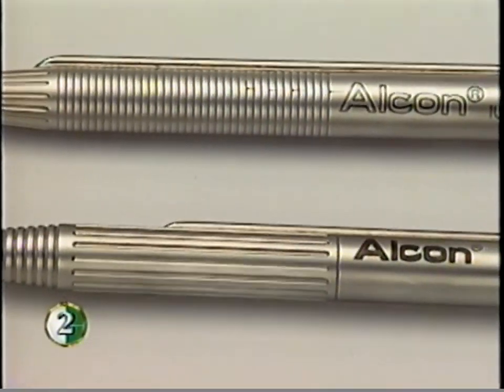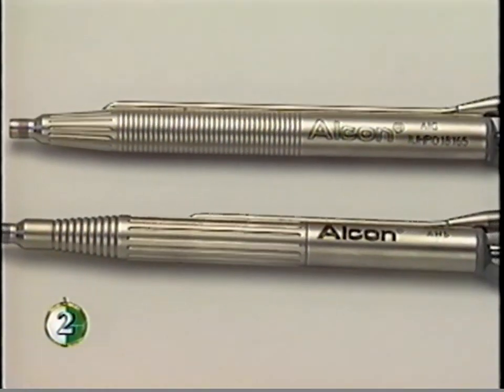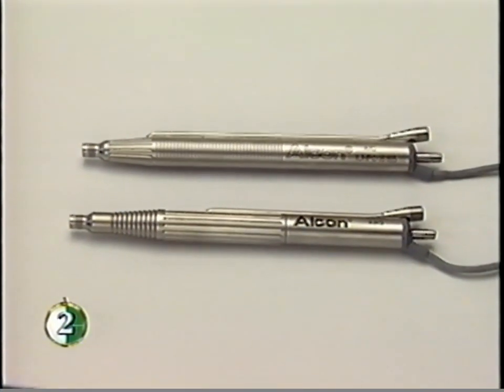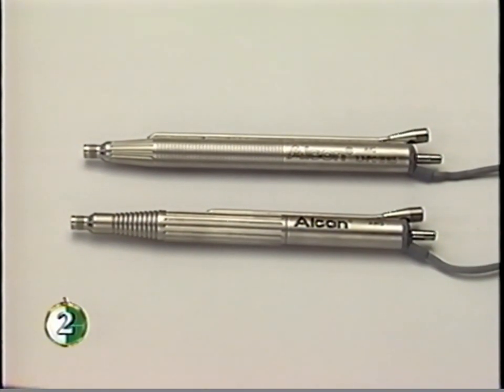In the ultrasound mode, ultrasonic handpieces integrate the functions of irrigation, aspiration, and ultrasonics. These handpieces, which come in 375 40 kHz and 375 60 kHz models, require no disassembly other than the removal of disposable tubing, the ultrasonic tip, and the infusion sleeve with bubble suppression insert, or BSI.